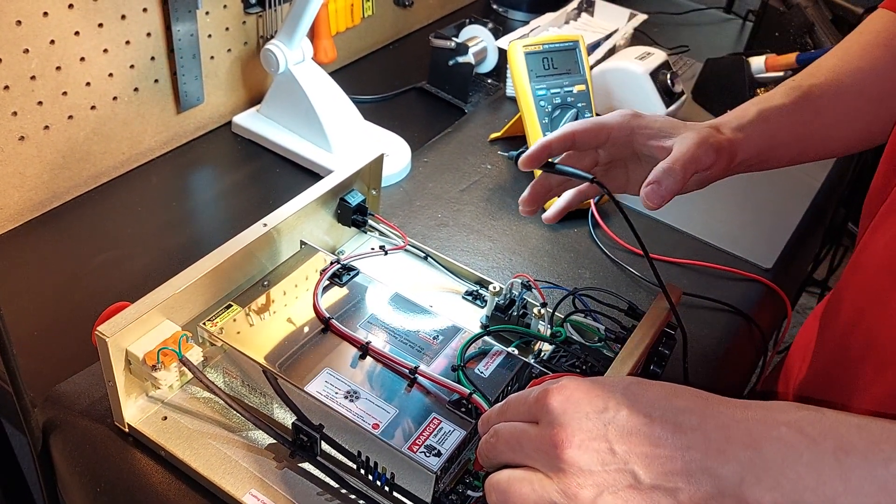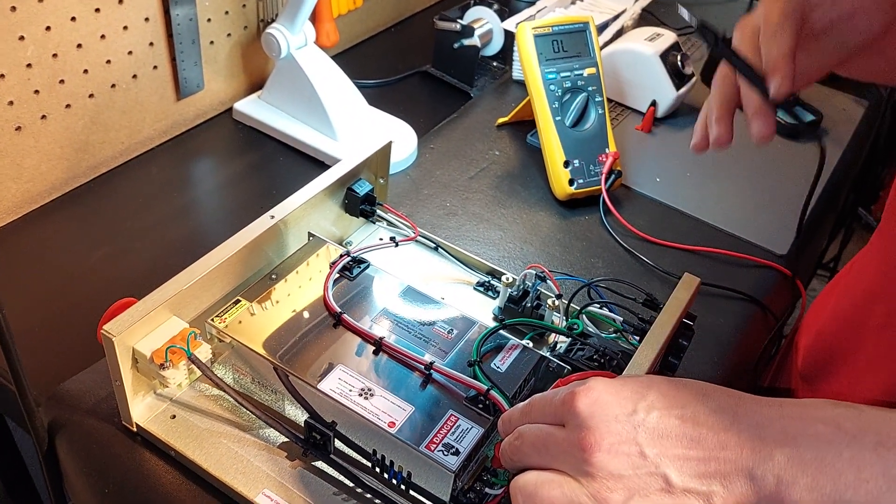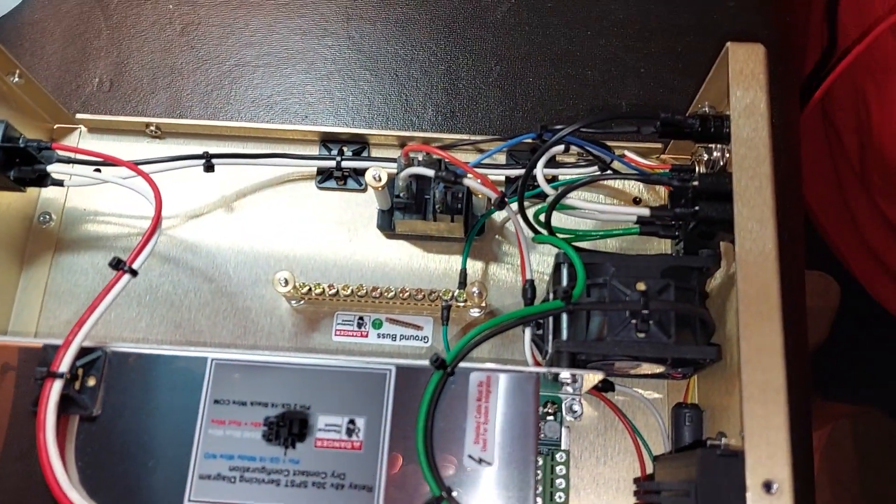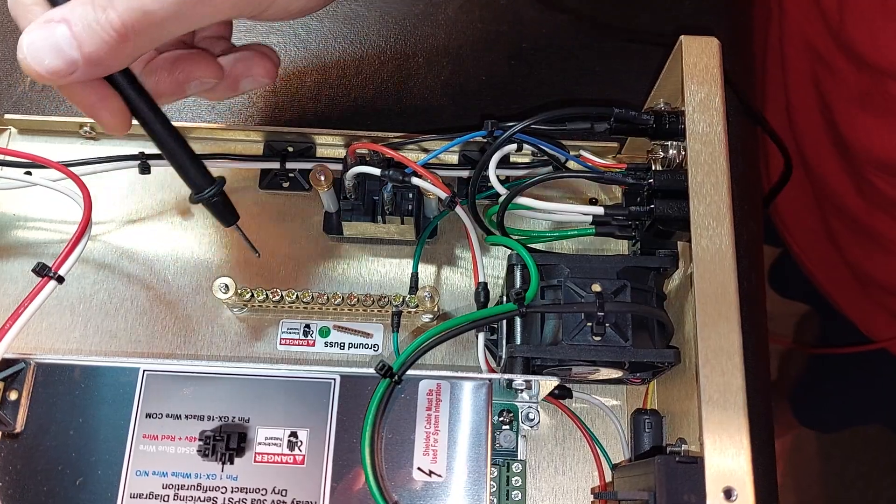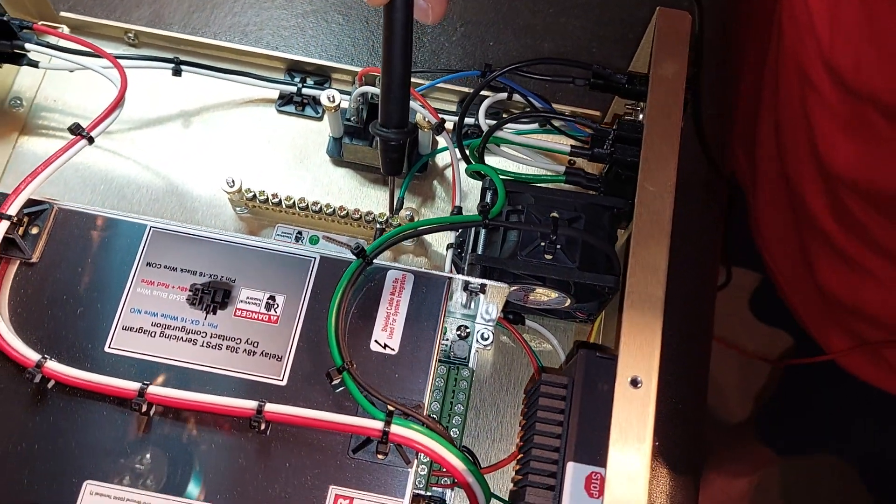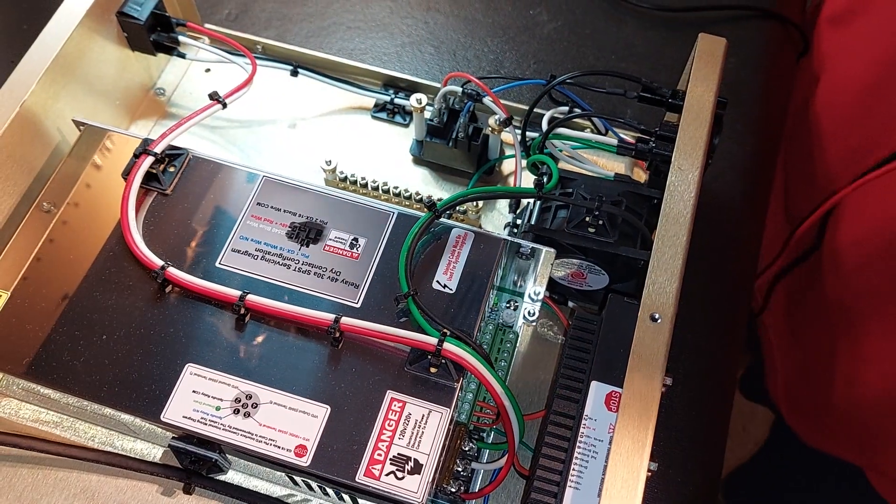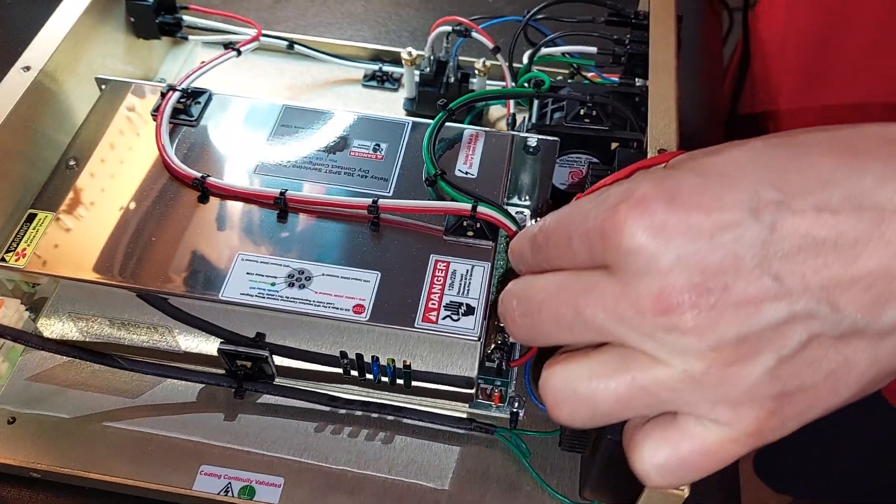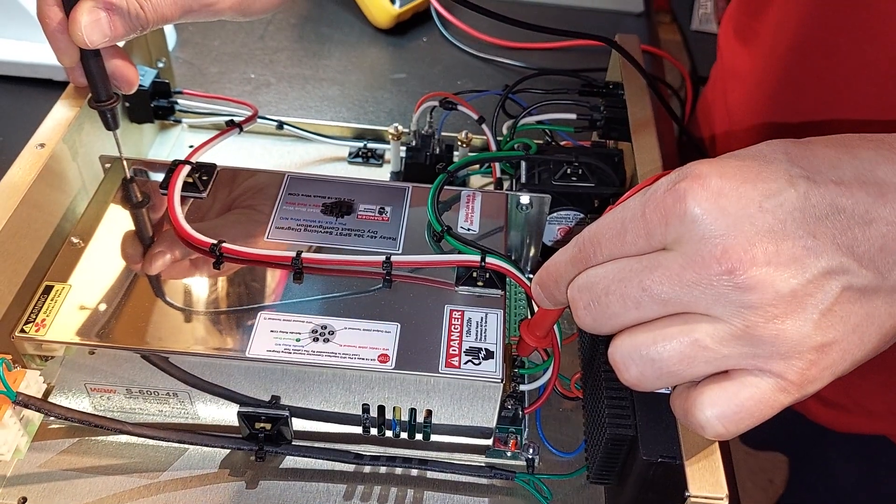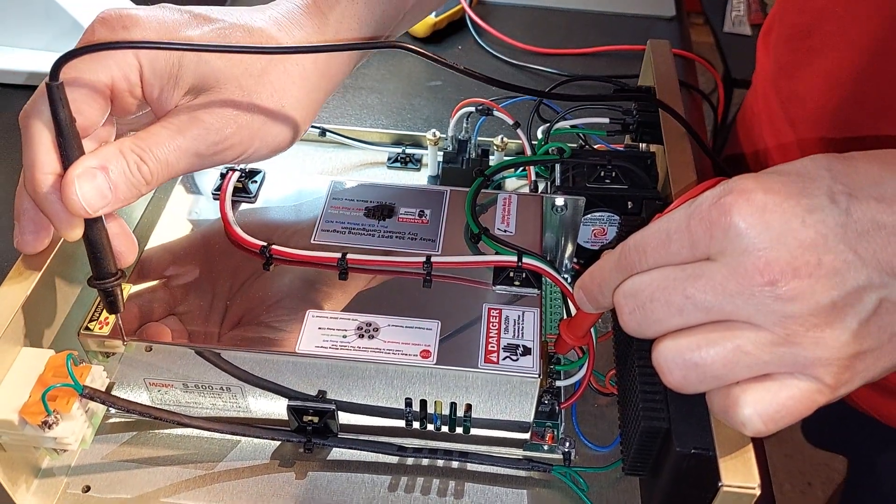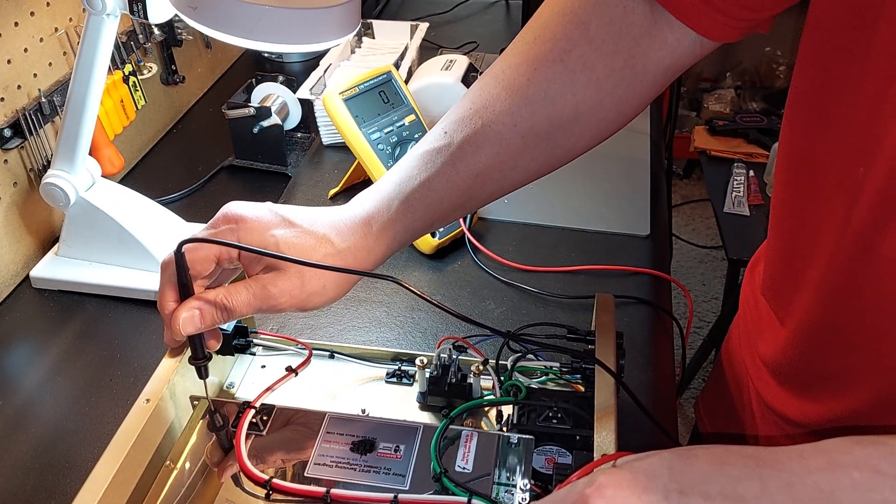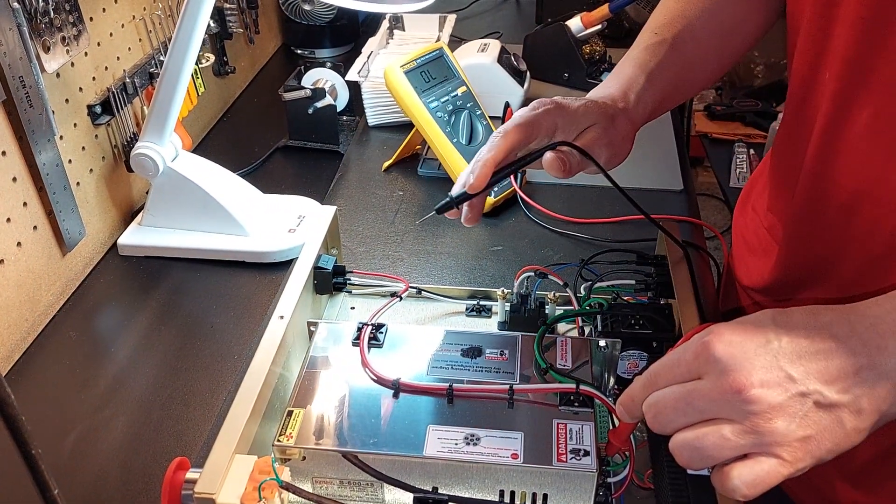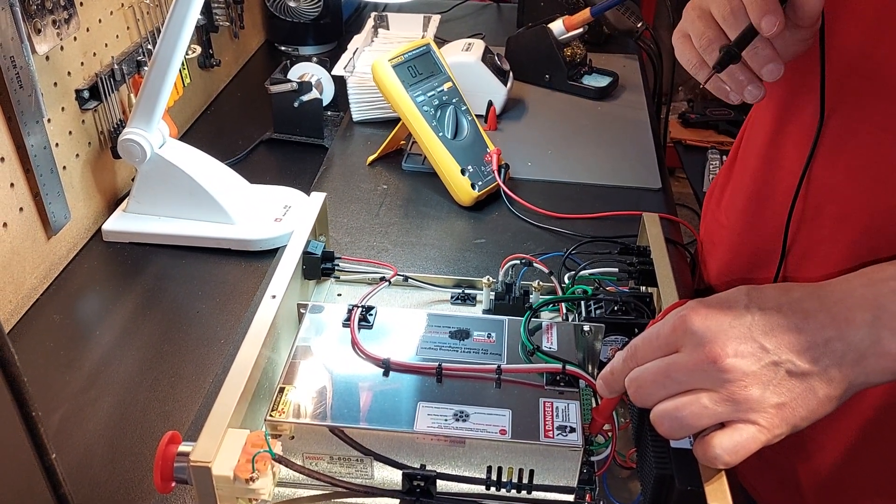You taking your time to understand this video, watch it again, and really take some notes and really go over in your mind how you're going to dictate developing your system, because this is the key right here. You want a central grounding point for your shield drains and whatever other accessory you're going to have here. If it needs to be connected to a central grounding point, then naturally do that. And then you want to wire in the controller so that the grounds are set up properly and double-check your power supply that you're using. I cannot tell you how many power supplies on the market are not properly grounded. And how do you test that? Well, just hit the ground on that power supply and hit the chassis on the power supply. So I'm hitting the ground terminal and I'm hitting the point on the chassis. You can do that anywhere. It should be totally conductive and you should be at zero. When you check the multimeter, I'm using a Fluke, I'm not playing games. I'm trying to show you guys why this is so critical, first of all for safety, and second of all to make sure that the system is going to provide the stability you're looking for.